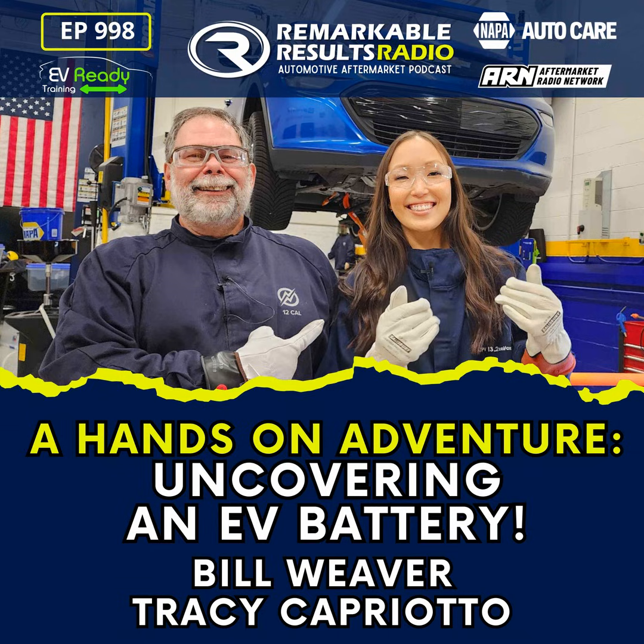One thing we're going to do is take our plastic non-conductive tool and start to separate the battery pack towards the front. Again, we want to make sure that gasket stays towards the bottom. Now that we've got it broken loose towards the front, take your hand - don't go too far in because we've got a battery inside there. Just on the flange, and we'll work our way back, separating the top of the battery from the gasket to make sure it's able to lift off and the gasket stays with the bottom.